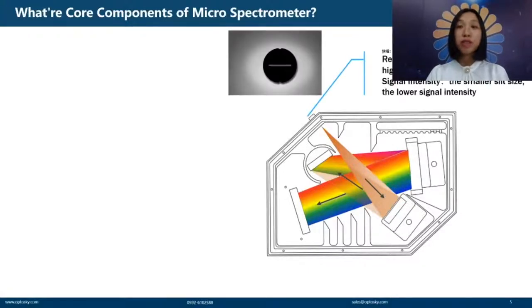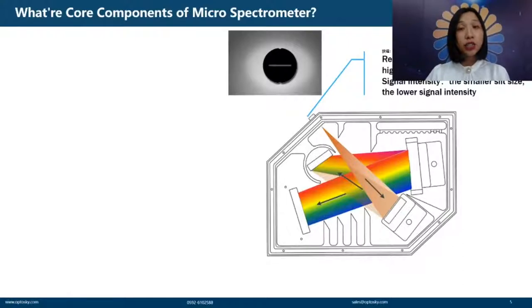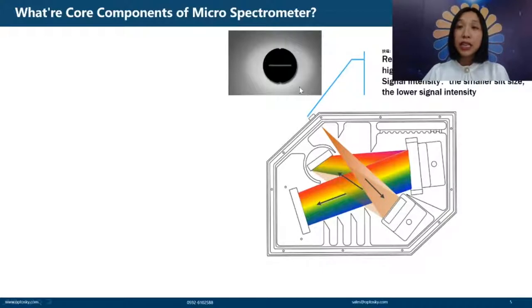First, we have the slit. The slit is used to form a point source. If the slit is narrower, the resolution is better, but the intensity is weaker.